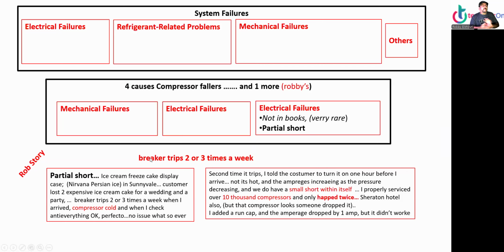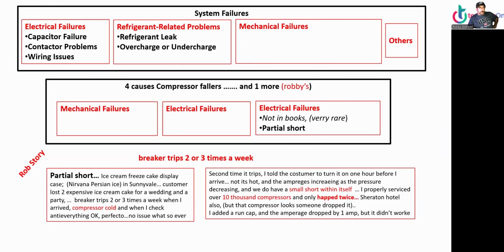All right, now, system failure and 4 causes of compressor failure. All right, so electrical failure. Okay. We have capacitor failures, contactor problems, wiring issues, refrigeration leaks, overcharge, undercharge, blockage.